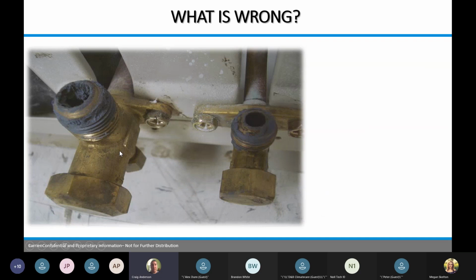This is another big one. If you're working on a unit and they got Loctite on the outdoor unit, they did not flare it right. They did not torque it down right. We don't want Loctite on our units. If the unit comes back and has Loctite on it, you will not get warranty on it. You'll notice the Loctite is inside the pipes. Once inside the pipes, it's going to get into the strainers. It's going to block your EE valve. It's going to do damage to the indoor unit. We're dealing with 1/4 inch line and 1/2 inch line. Anything that's obstructing flow, kinks, blockages, anything like that is going to disrupt your flow to your indoor and outdoor unit. So be mindful of kinks, Loctite, anything like that.